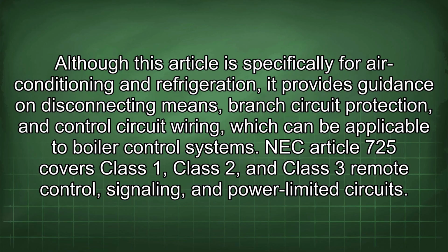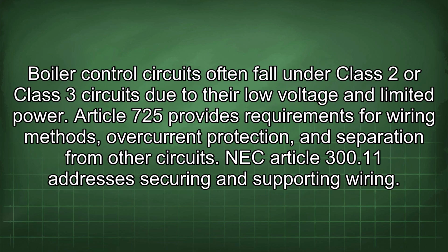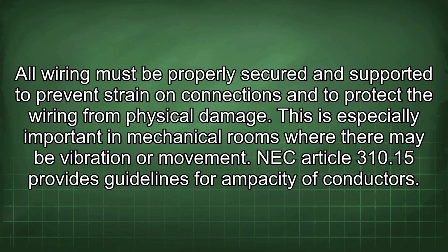NEC Article 725 covers Class 1, Class 2, and Class 3 remote control, signaling, and power-limited circuits. Boiler control circuits often fall under Class 2 or Class 3 circuits due to their low voltage and limited power. Article 725 provides requirements for wiring methods, overcurrent protection, and separation from other circuits. NEC Article 300.11 addresses securing and supporting wiring. All wiring must be properly secured and supported to prevent strain on connections and to protect the wiring from physical damage. This is especially important in mechanical rooms where there may be vibration or movement.